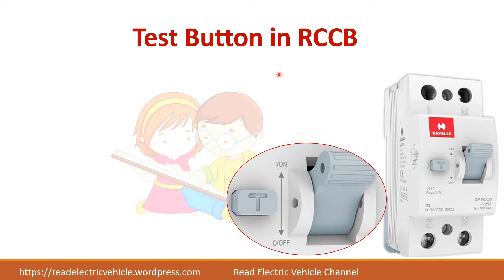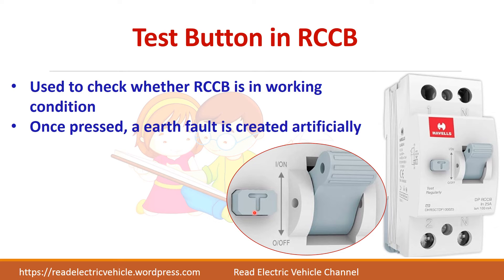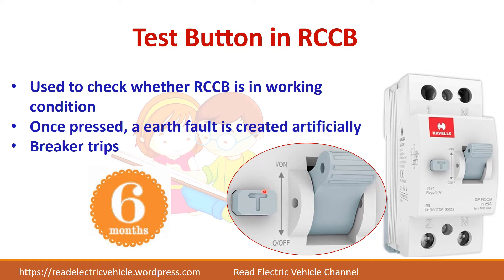Next, we will see about the test button available in the RCCB. You can see a symbol 'T' on the test button. This is used to test whether this particular RCCB is in working condition or not. Once you press this button, an earth fault will be artificially created inside and the breaker will trip. If it doesn't trip, it means that the RCCB has to be replaced or it is not working properly. It is advised by the manufacturer to test the RCCB at least once in six months, and some manufacturers even recommend testing every month.